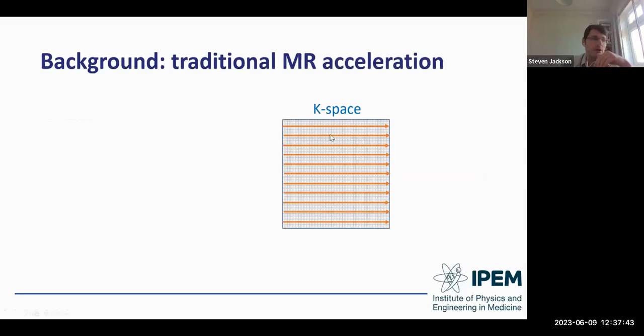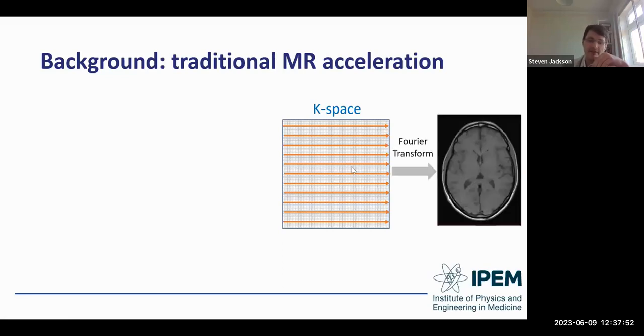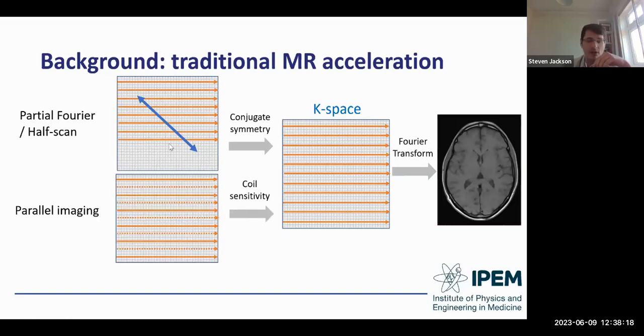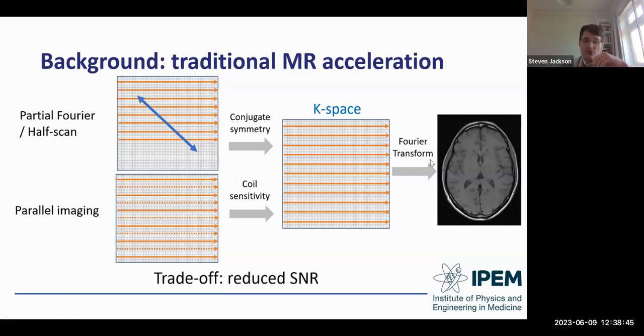MR images are acquired line by line in K-space, and that information is then Fourier transformed into the final image. Partial Fourier or half scan acquires a subset of K-space — for example five-eighths, six-eighths, or seven-eighths — and uses mathematical symmetry properties of K-space to fill in the rest before reconstruction. With parallel imaging, you skip a certain number of lines of K-space, for example every other line, then use information about receive coil element sensitivities to fill in the rest of K-space and reconstruct the image. Both methods allow faster acquisition but the trade-off is reduced signal-to-noise ratio.